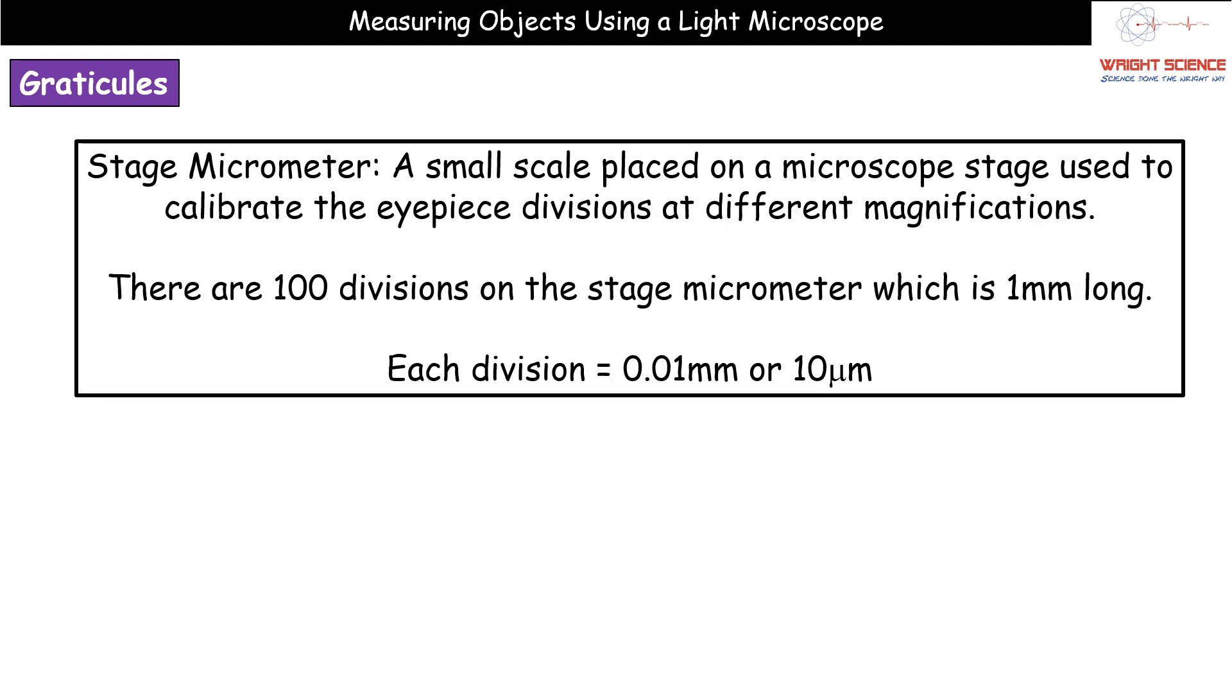Now the stage micrometer quite simply is a small scale that's placed on the stage of the microscope that we use to calibrate those eyepiece divisions. The reason we've got to do that is because each of the different objective lenses will have a different value for it. So we need to use this stage micrometer with each of those different objective lenses first to calibrate, to know how much those values correspond to for each of our objective lenses.